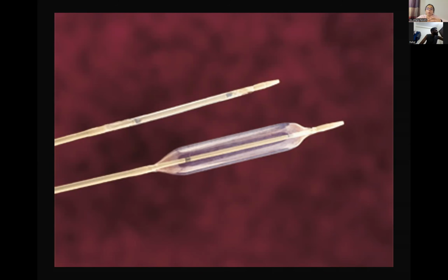But when you are opening up a blocked peripheral artery, say you're opening up the femoral artery or the iliac artery, you need a stiff balloon so that it can open up a very tight stenosis. So that's where stiff balloons are used. And sometimes the plaques are calcified plaques or very thick plaques. That's when you use cutting balloons, which in addition have cutting blades on their edges. They usually have 3 radially arranged cutting blades, and they're used to cut through the plaque and assist in angioplasty.